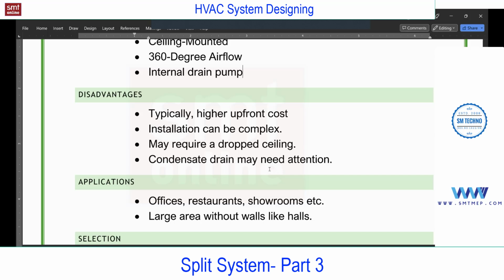If any leakages from the drain, that will damage the false ceiling if it is a gypsum board, or it may cause electrical issues in case of this leakage of water. And drop ceiling is required anyhow. With the false ceiling only we are using, so we cannot consider this a disadvantage. Without false ceiling we'll not use this. So with false ceiling, as per the interior requirement only, we can use this one.